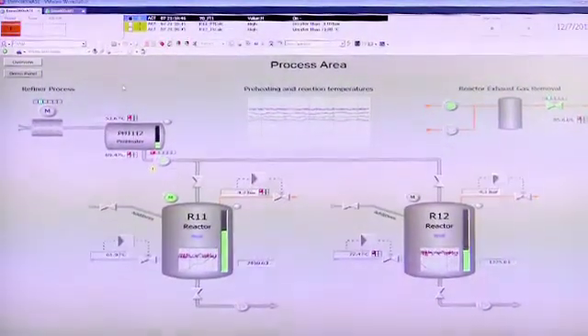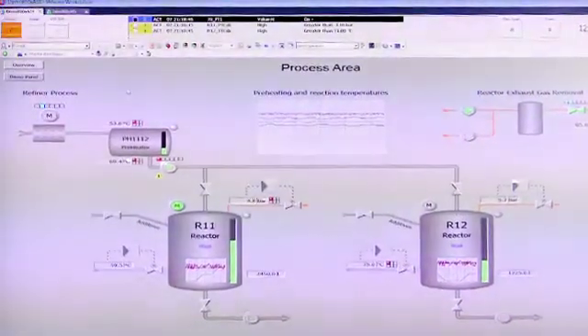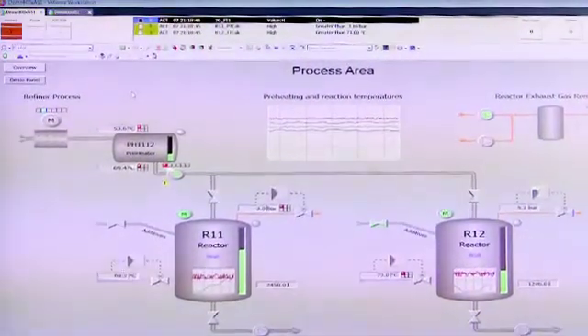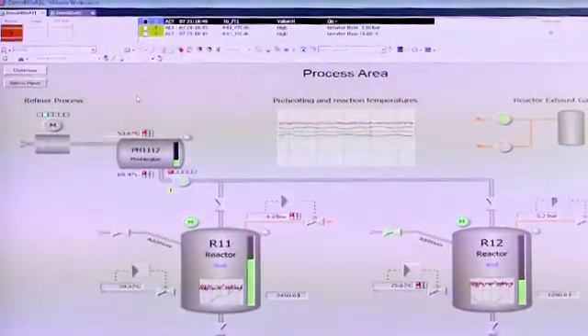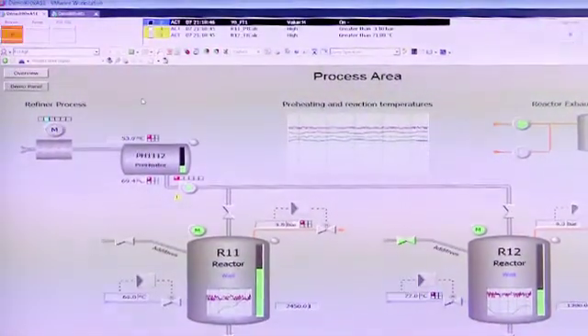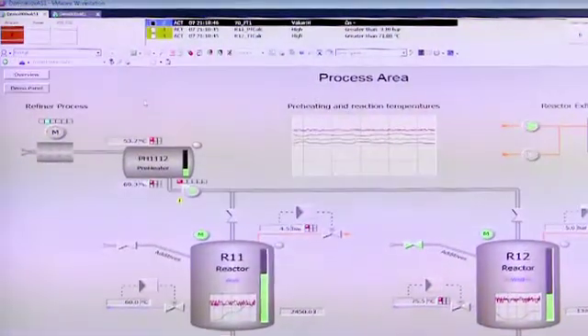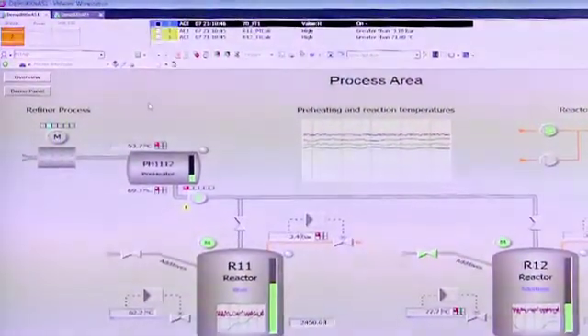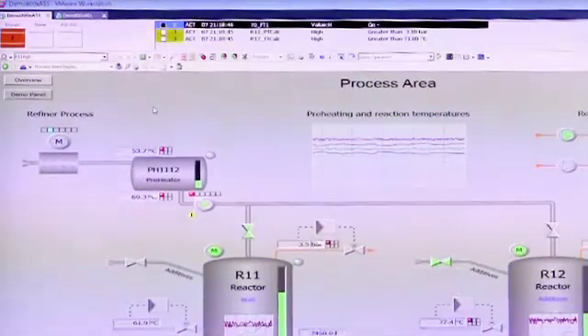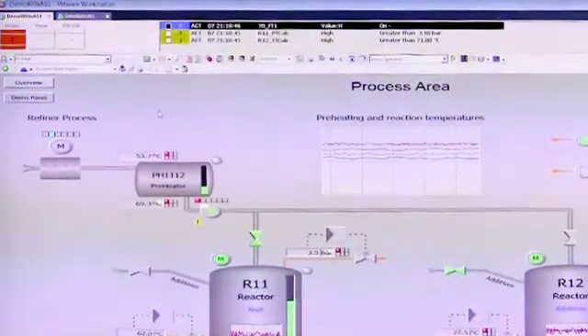Alarm shelving is where an operator can temporarily suppress an alarm from their alarm list, or shelve it, for a certain duration and time. This capability is listed in various guidelines and standards such as EEMUA 191 and ISA's SP18.2, and can reduce the amount of nuisance alarms that may interfere with operators taking action on valid process alarms.